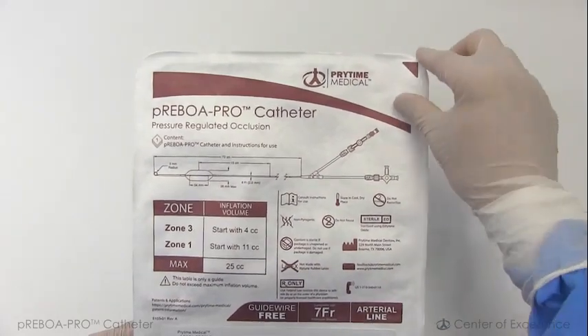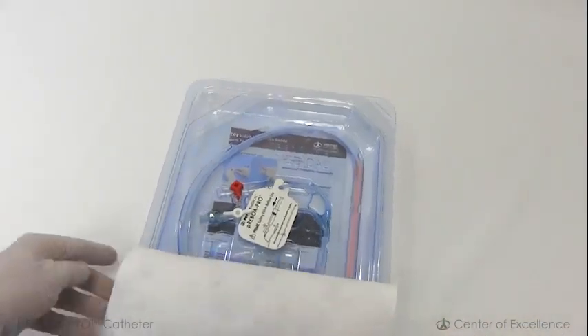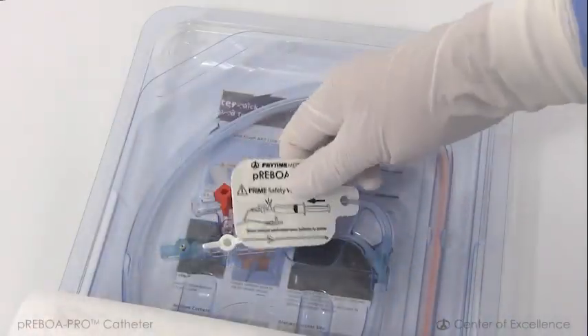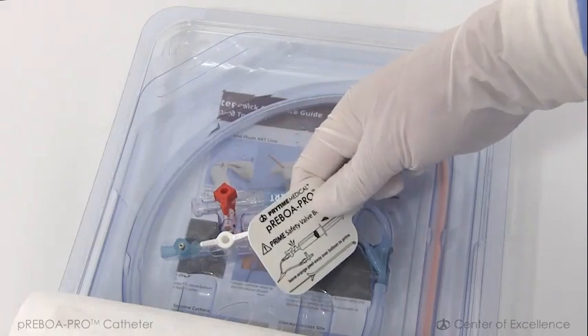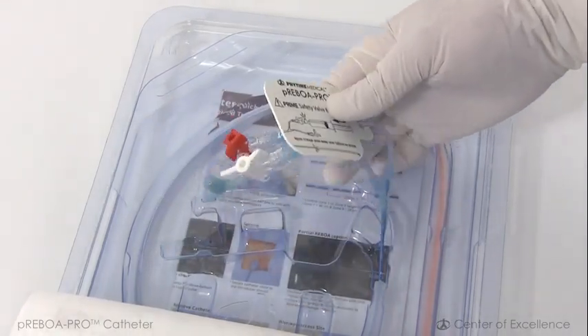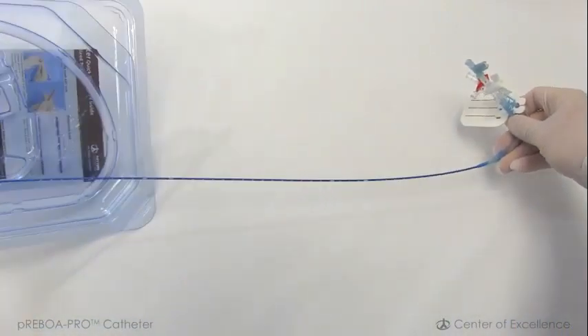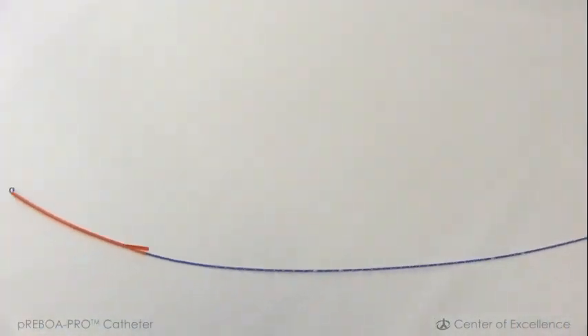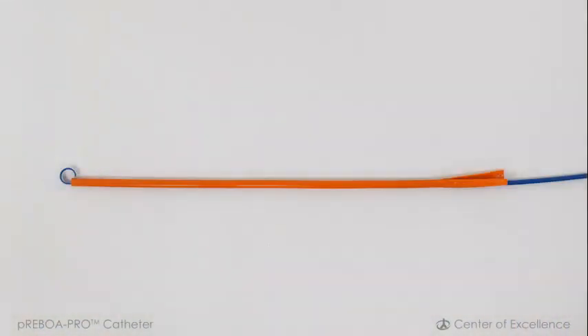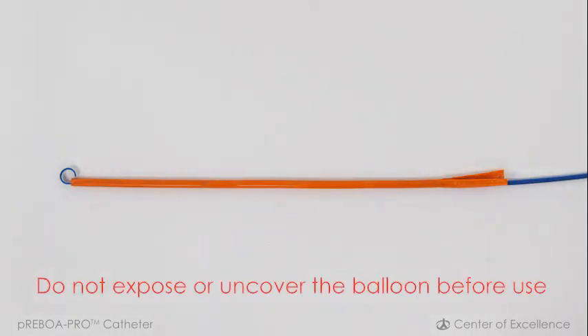To open the tray, peel back the Tyvek lid from the upper right and remove the catheter. Insert your fingers below the extension lines. Lift the extension lines until the stopcocks pop away from the tray. Then simply pull the catheter out of the box. When you receive the pREBOA-PRO catheter, the balloon has been specially manufactured to be ready for immediate insertion. It is not necessary or recommended to unsheathe the balloon or insert air or liquid before use.